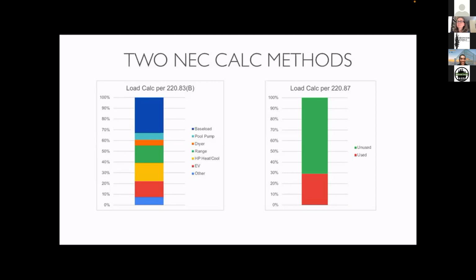In my case, it was just shy of 30% over the last 12 months, meaning I still have 70% of my panel or service line available to use. So the two methods come up with different answers, and depending on the situation, the code allows you to use one or the other. There are situations where it makes more sense to use 220.83b—I won't go into that now—but I just want to make the point that the code has some flexibility and allows us to use different calculation methods depending on the situation.